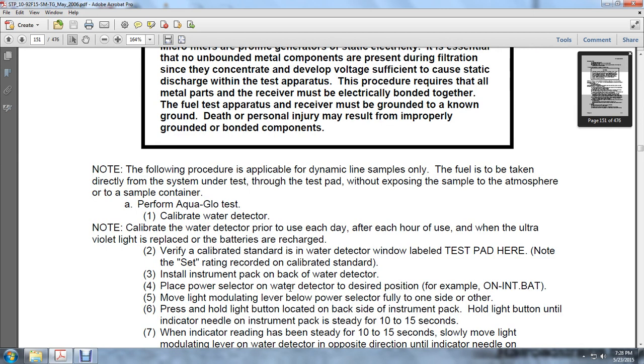The following procedures are applicable for dynamic line samples only. The fuel is to be taken directly from the system under test through the test pad, without exposure of the sample to the atmosphere or to a sample container. Perform the Aqua-Glo test. Calibrate the water detector. Calibrate the water detector prior to use each day.